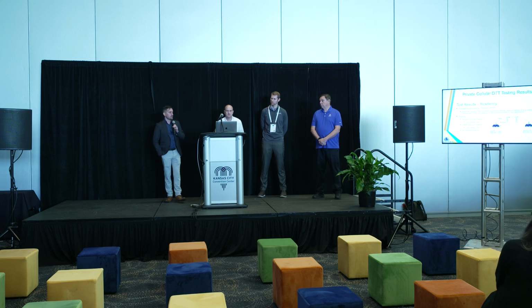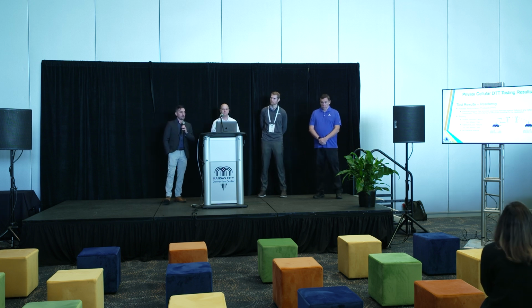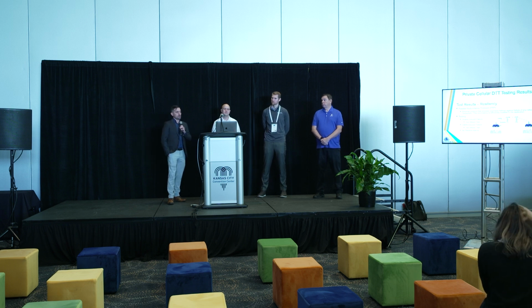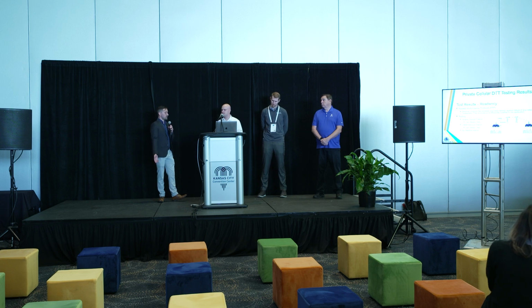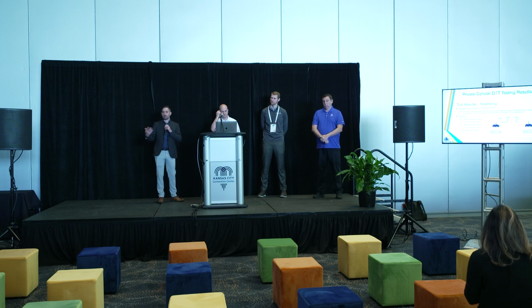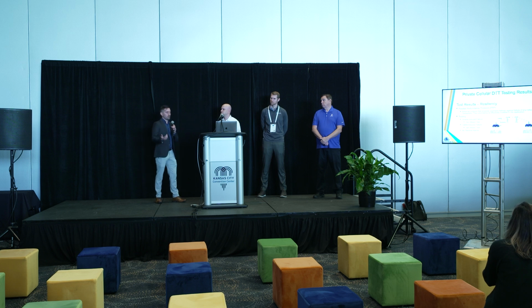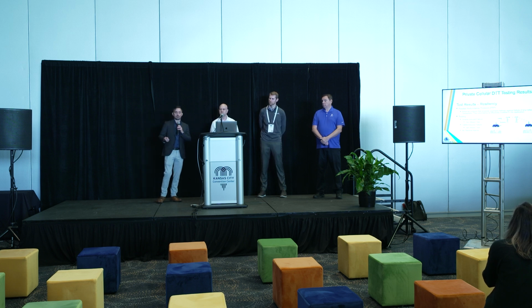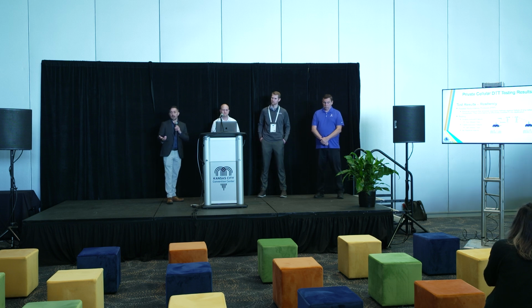The other piece that Brian talked about earlier is that resiliency, using PRP. The reason we do that is so that we can have seamless failover. After we got some good baseline numbers and saw that we had 100% trip rate, no failures, we started inducing failures into the network. So how do we test that seamless failover? We tried a few different ways. We were disconnecting Ethernet ports, taking network equipment down, taking eNode Bs down, things like that, just trying to simulate some real world failures.